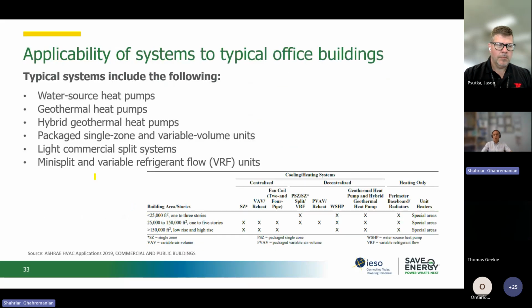ASHRAE has this nice table which compares different systems depending on the size of the building, either a VAV, variable air volume, or a water source heat pump, either as a decentralized system or as a centralized system. Every one of them you can see in ASHRAE, and it helps with the design. So we can consider, as I said, the geothermal ground source heat pump, or we can consider a hybrid ground source heat pump, or a packaged single-zone or variable volume unit. For light commercial, we can consider a split system, or if we can afford it, we go with a mini split or variable refrigerant flow units. Again, each of them is presented in the ASHRAE standard.